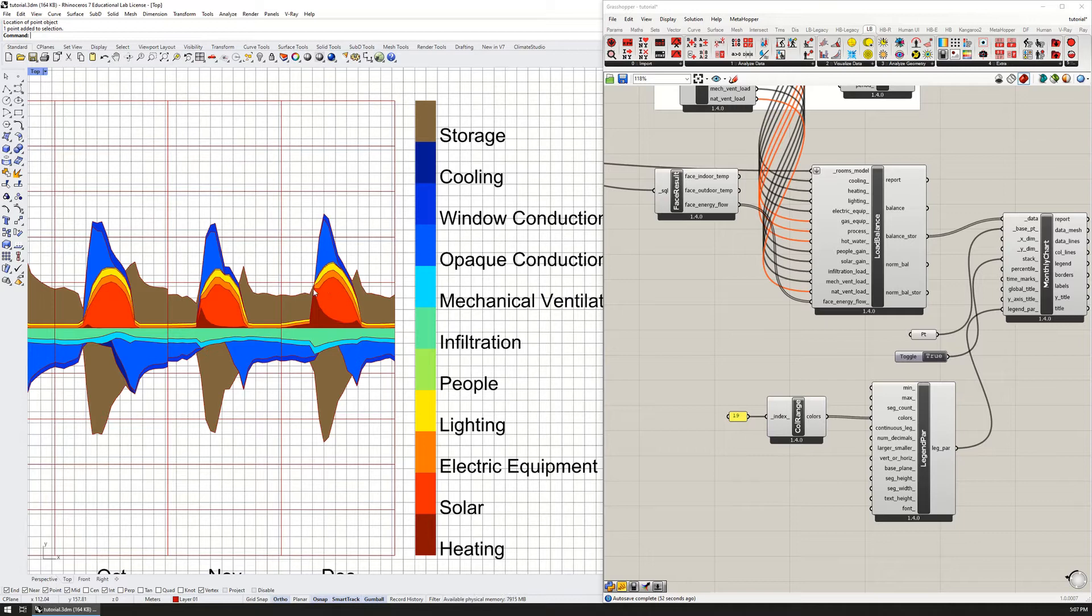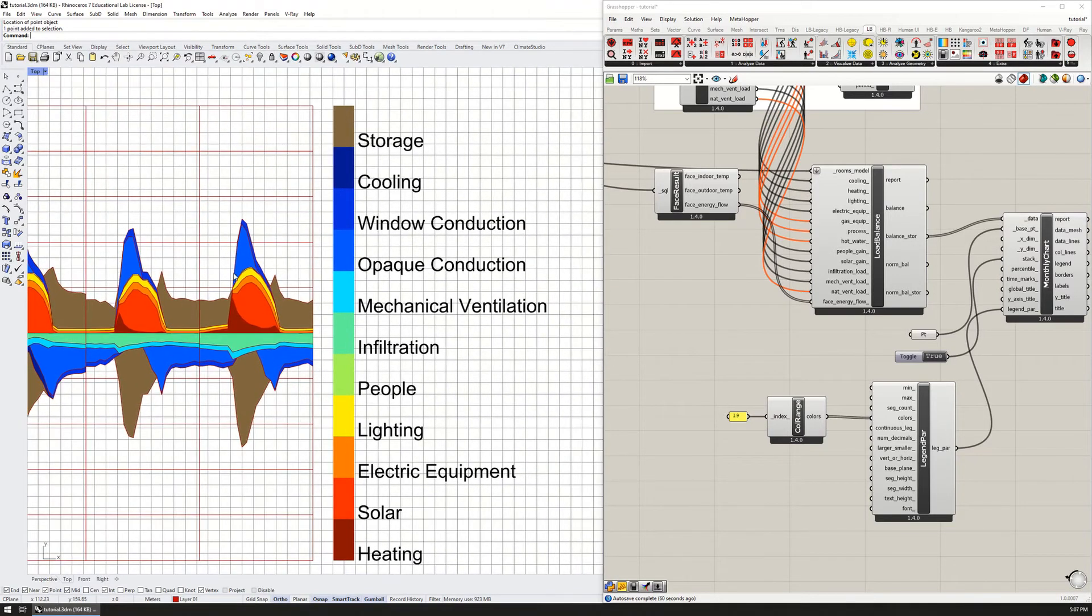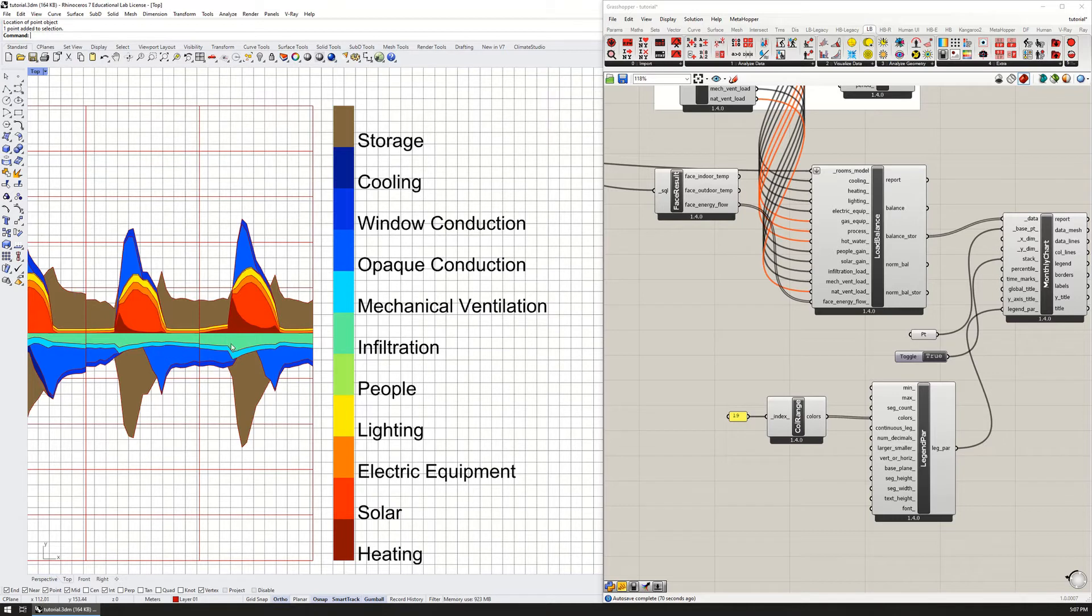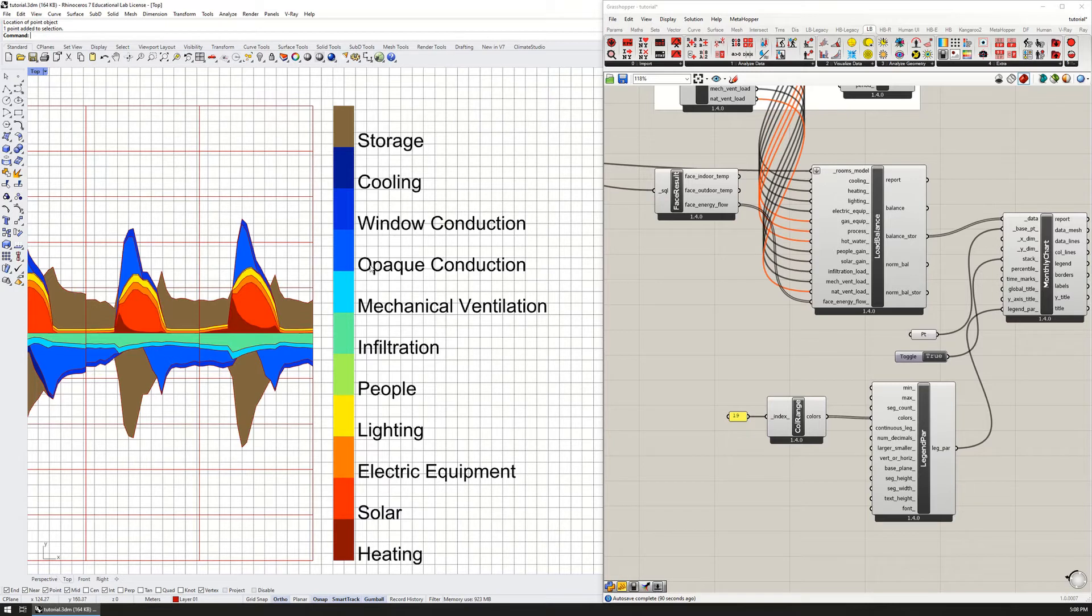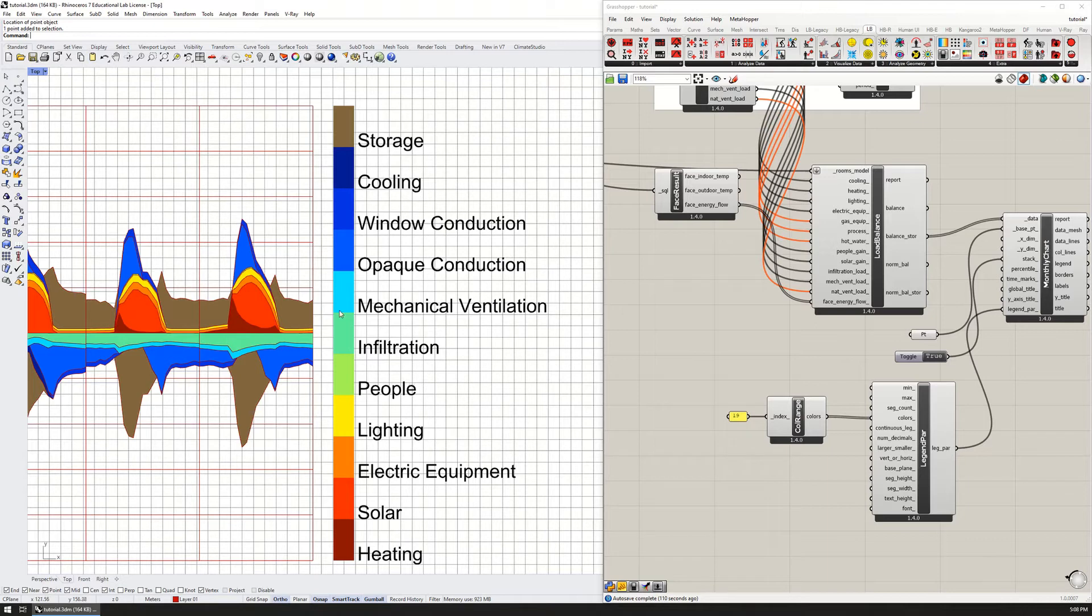If I come back over here so we can see the key, you can see that the main gains here - we have the HVAC system turning on in the morning and then going down as the solar ramps up in the afternoon. The electric equipment is adding to the heat along with the lighting, and then the opaque conduction through the envelope is heating the room up, as is the window conduction. On the minus side, we are losing heat based on infiltration, mechanical ventilation, opaque conduction later in the day, and then the rest of what we're losing is the mass storage. Together all these gains and losses equal zero as a balance.